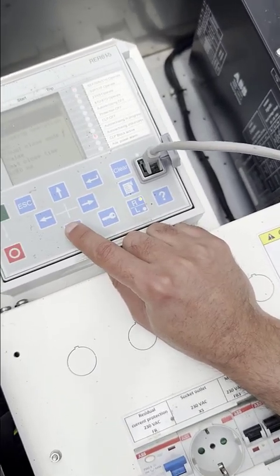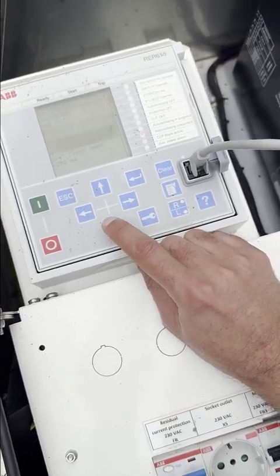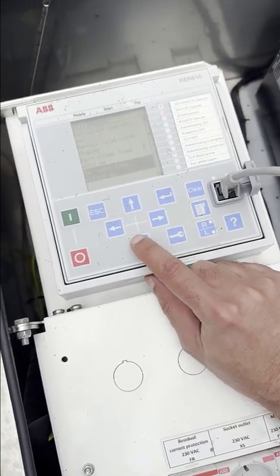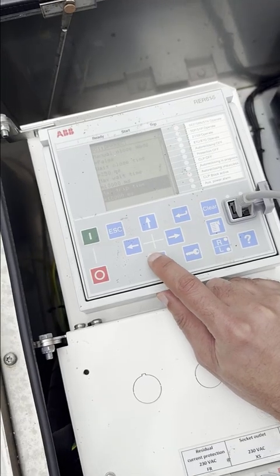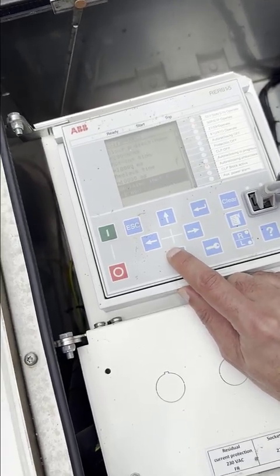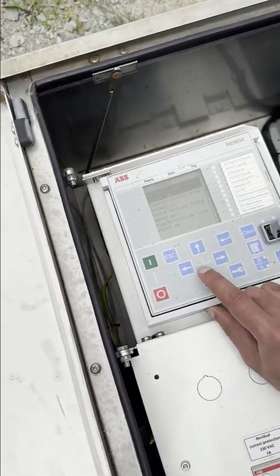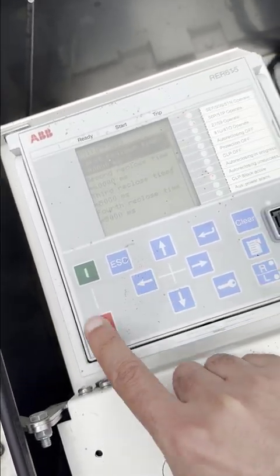So you can see the operation is on, and here is the closing operation. Here is the manual close mode, and the wait time, and the maximum wait time is 10 seconds. The reclaim time is also 10 seconds. So here is the first reclose time, which is equal to 30,000 milliseconds, which means 30 seconds.